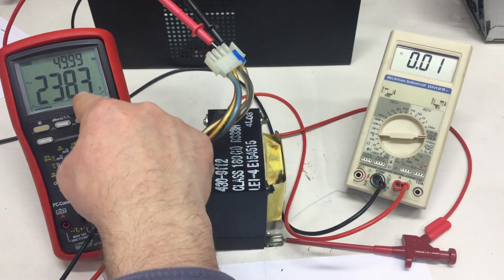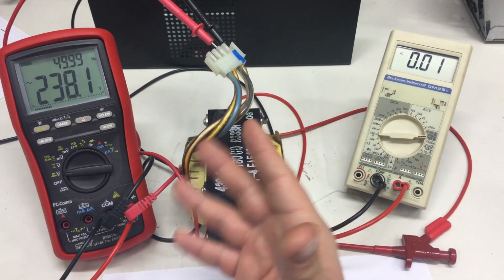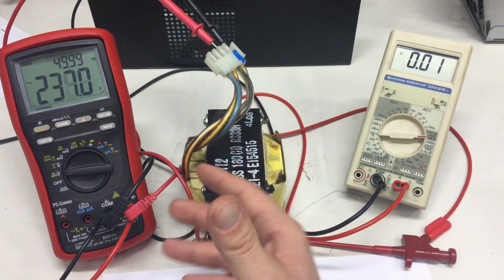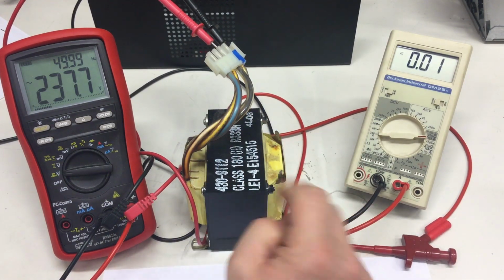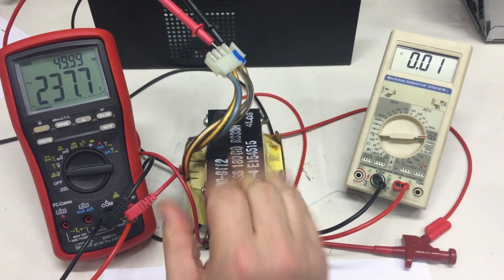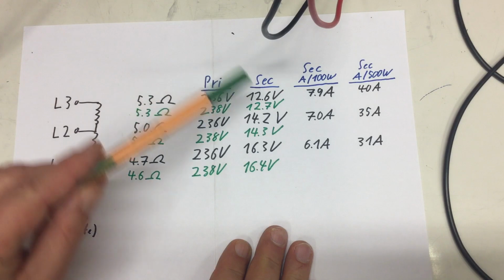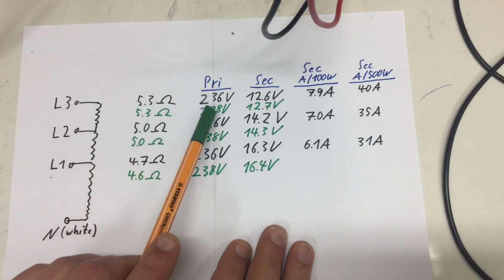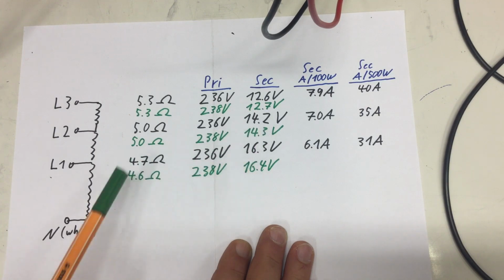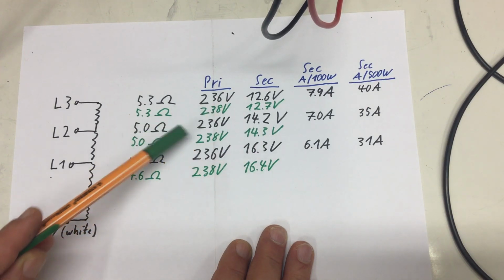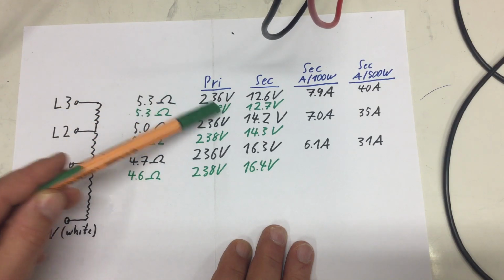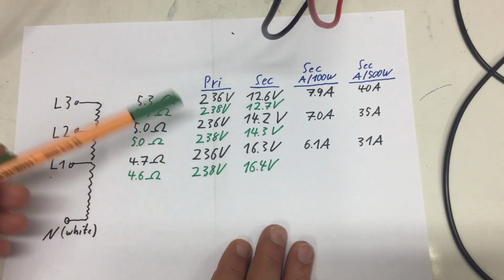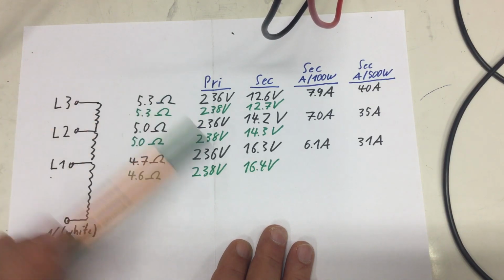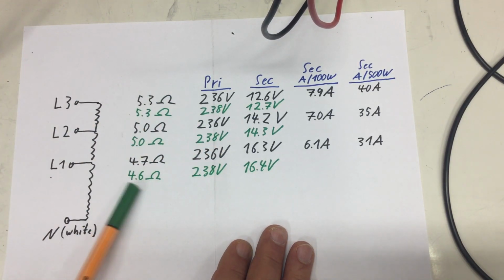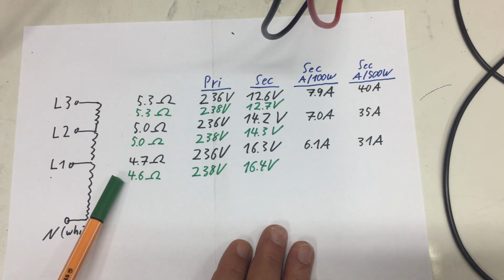You need to test for higher voltages, okay? And you need special test equipment to do that and to really actually read the isolation values in ohms, between the primary and secondary. I tested the other transformer too. That are the green values, and they are nearly identical. My mains AC has risen in the meanwhile by 2 volts. That's, it's 230 volts plus minus 10%. So everything seems to be in order. One digit, the least significant digit here, is off by 0.1 ohm on the primary, but okay.